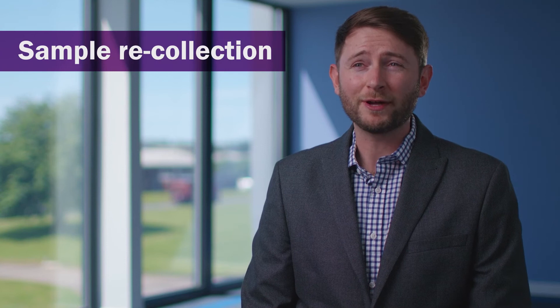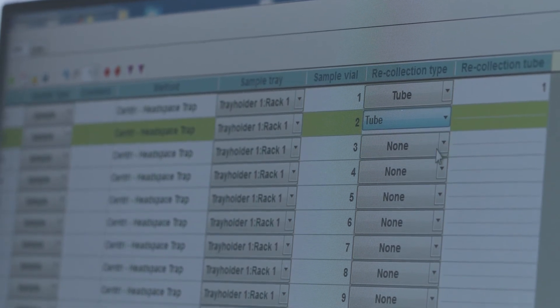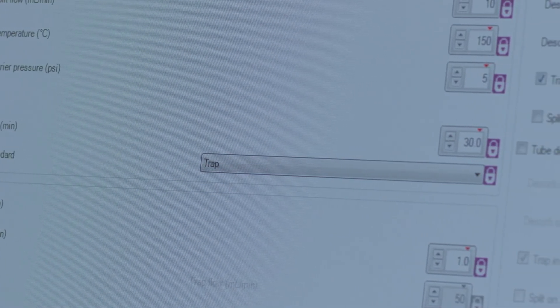Our trapping technology has a range of different benefits, but one worth mentioning is recollection — to recollect the split portion of the sample when it's injected to the GC. We're now able to employ this with all of the sample introduction techniques that utilise the trap on CENTRI. We can now offer recollection for techniques such as headspace and SPME, where it's never been offered before.